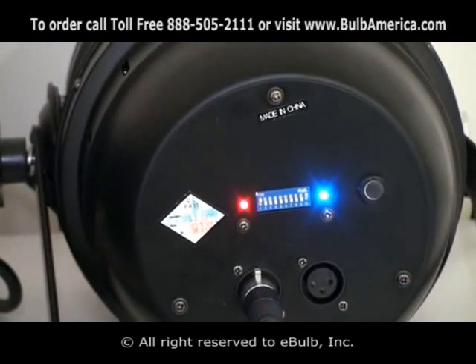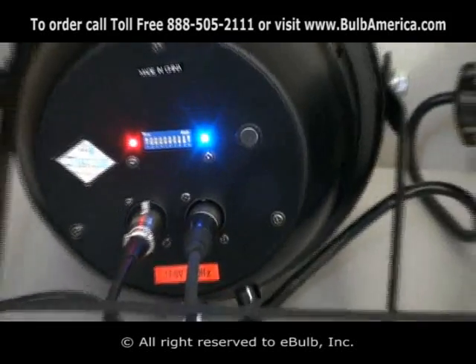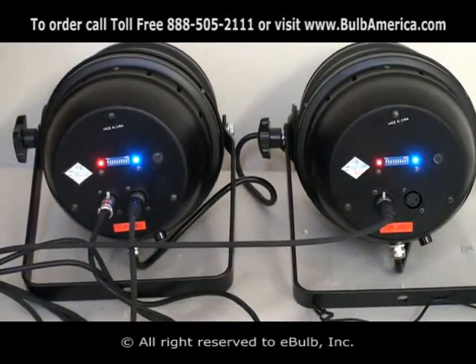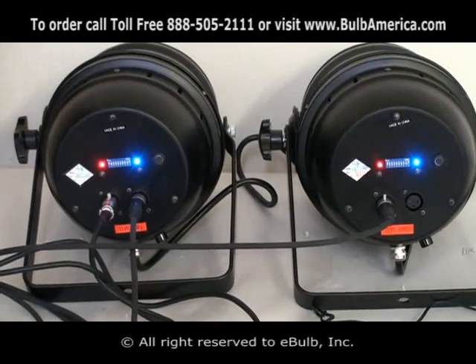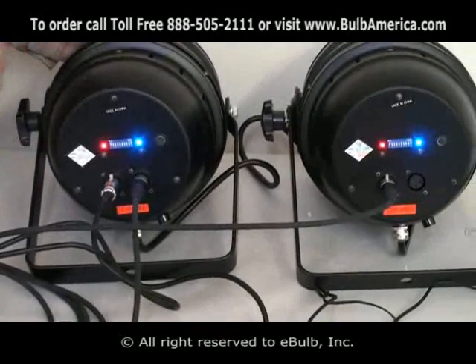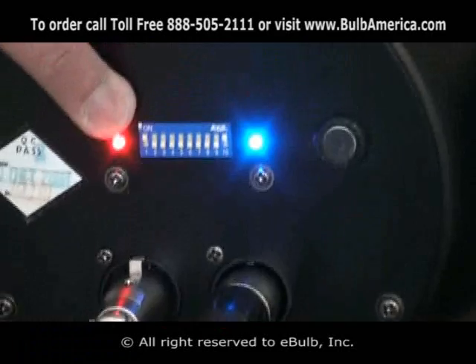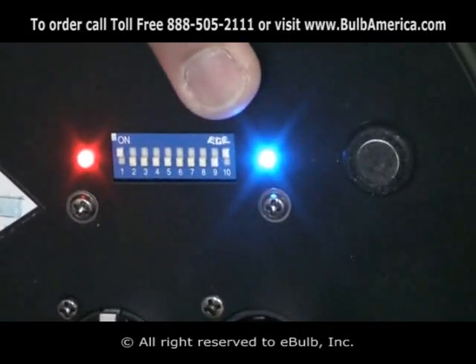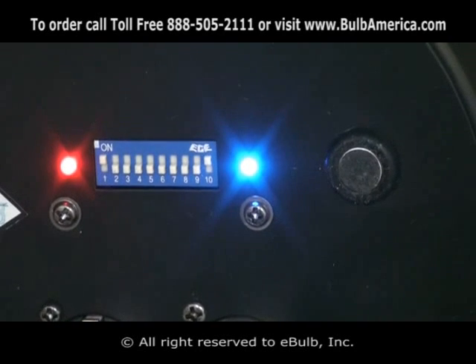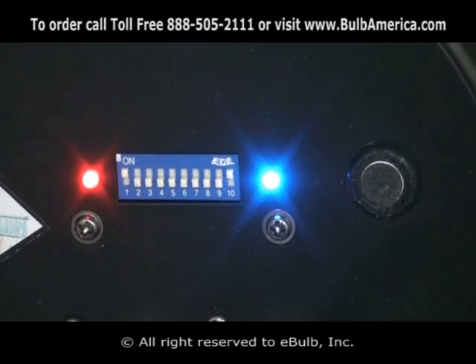As I indicated in the earlier video, it's very, very important to make sure that all the DIP switches are set to the off position before you plug the units in. The setting that has to be set on this unit, when configured this way, is DIP switch number 1 on and DIP switch number 10 on. These two DIP switches have to be set on all four units prior to connecting to power.